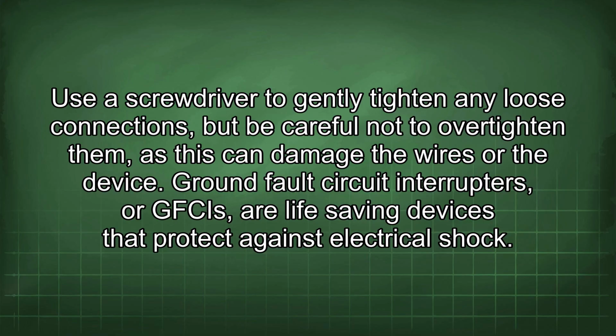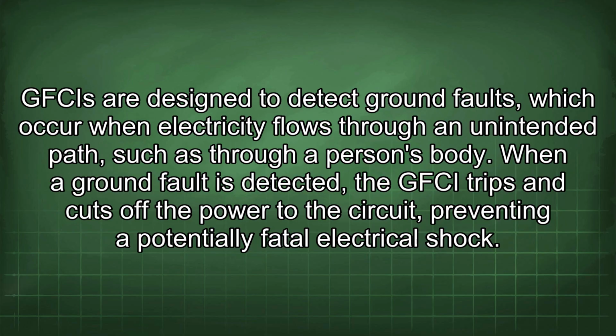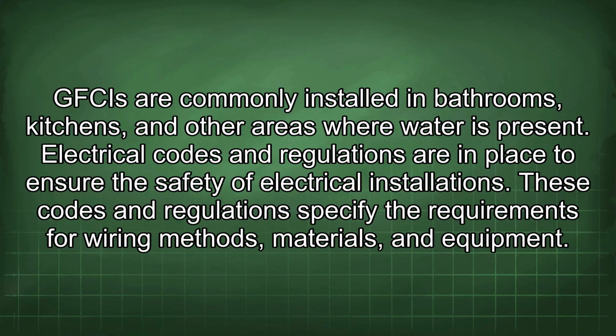Ground fault circuit interrupters, or GFCIs, are life-saving devices that protect against electrical shock. GFCIs are designed to detect ground faults, which occur when electricity flows through an unintended path, such as through a person's body. When a ground fault is detected, the GFCI trips and cuts off the power to the circuit, preventing a potentially fatal electrical shock. GFCIs are commonly installed in bathrooms, kitchens, and other areas where water is present.